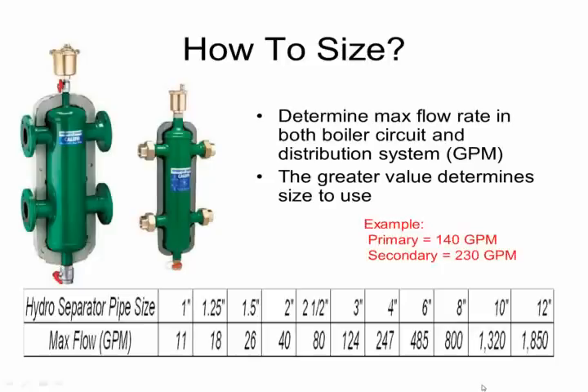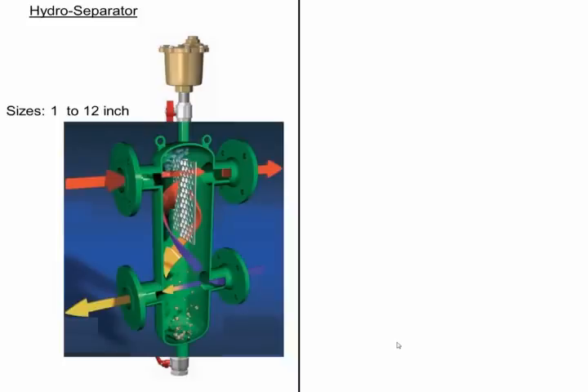So how do you size a hydraulic separator? It's very simple. You take the maximum flow rate under design conditions in your primary circuit, and the maximum flow rate in your secondary circuit. The greater of the two determines what size hydraulic separator you use. So as an example, if we had 140 and 230, that would put us into a 4-inch hydraulic separator.